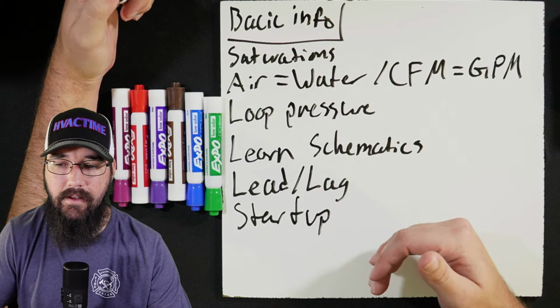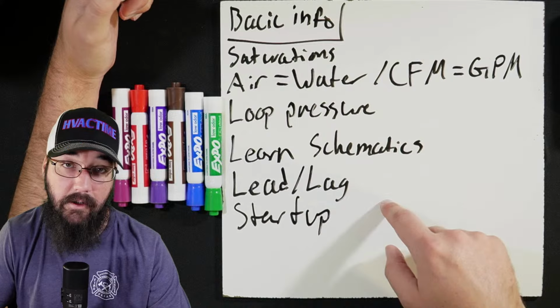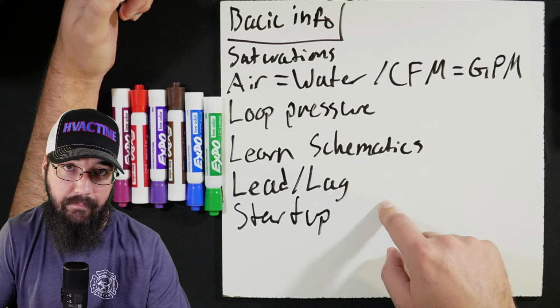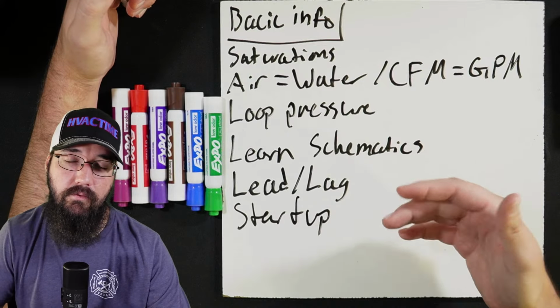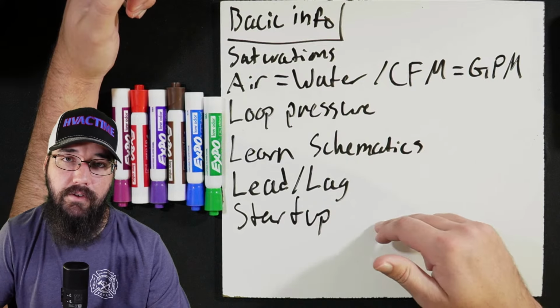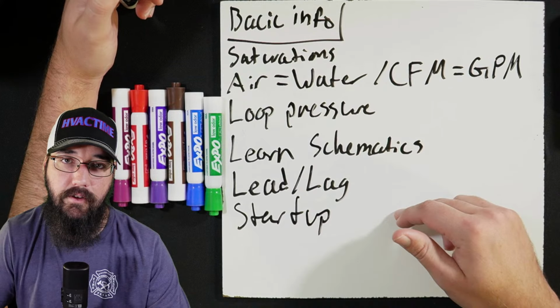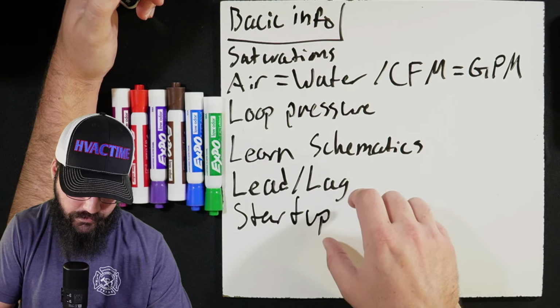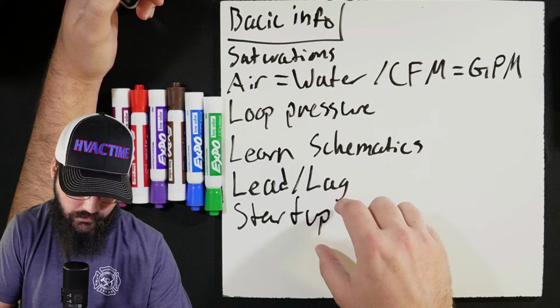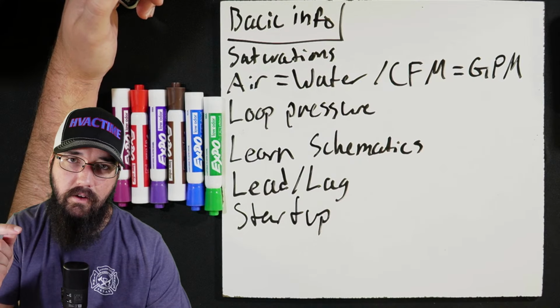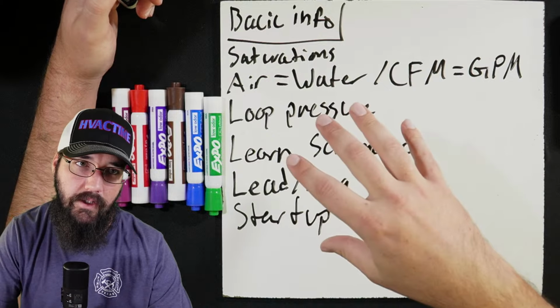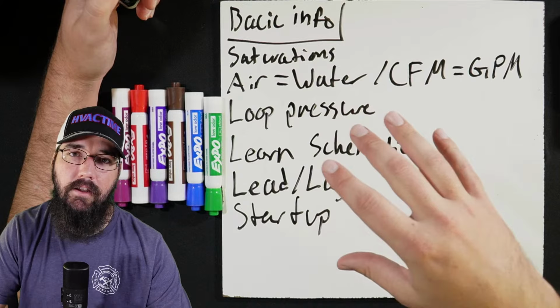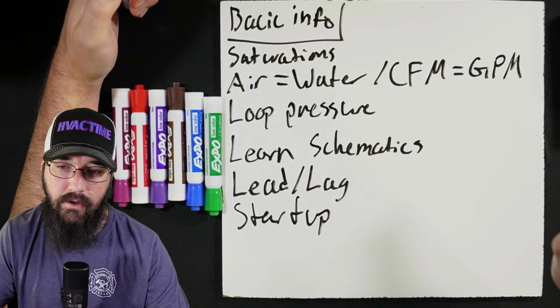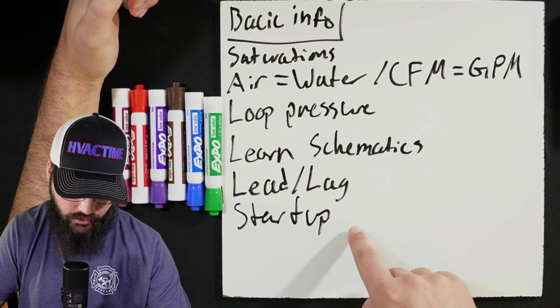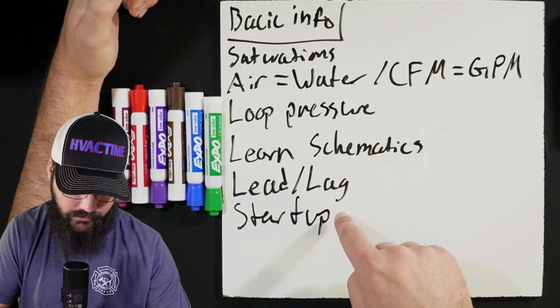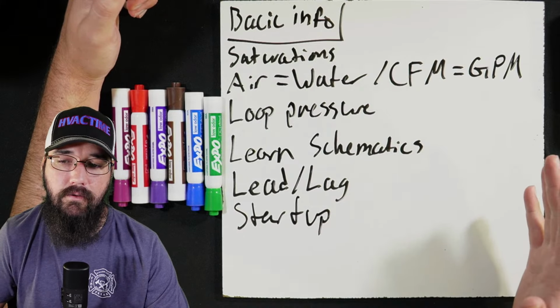It's going to be to establish airflow, right? Same thing on the chiller side. When we first get told to turn on, what's the first thing we need to establish? Water flow. So even from just an RTU perspective, if you can really get your head around RTU staging, like startup specifically, then you'll have a lot to bridge over into how chillers work.